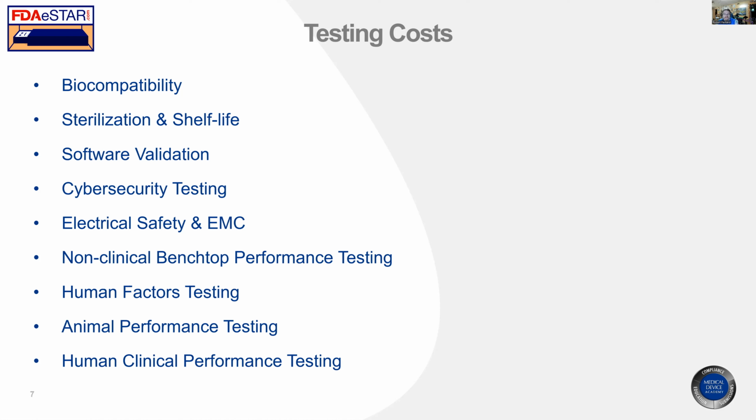And I'm not even kidding here or exaggerating. I have received an 80-page checklist asking me on what page of your risk management file can we find this information. And a lot of sections will be not applicable, but you've got to go through the 80 pages and figure out what's not applicable, what is, and what page it's on. So that's an extensive amount of work. So you really need to work on software, human factors, and risk management before you can even start your electrical safety. And in parallel with those three, you're doing EMC testing. So this is not quick if you have an electromedical device.